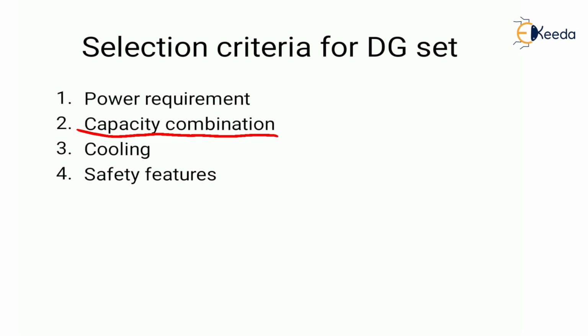And the last point is safety features. It is advisable to have short circuit, overload, and earth fault protection in all the DG sets. However, for a smaller capacity DG set, it becomes uneconomical. Hence, it is recommended to install a circuit protection. Other safety equipment like high temperature and low lubricant oil pressure cutout should be provided so that in the event of any abnormality, the engine would stop and prevent damage. It is also essential to provide a reverse power relay when the DG sets are to run in parallel to avoid backfeeding from one alternator to another.